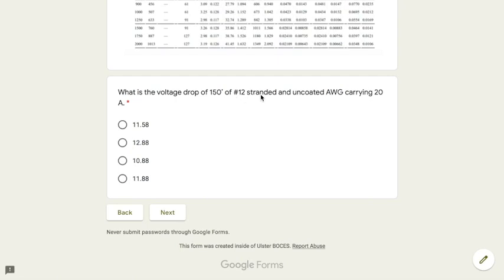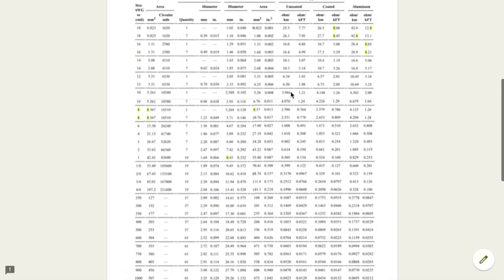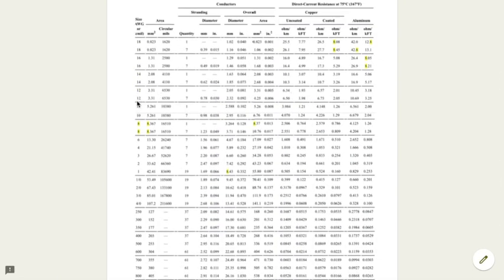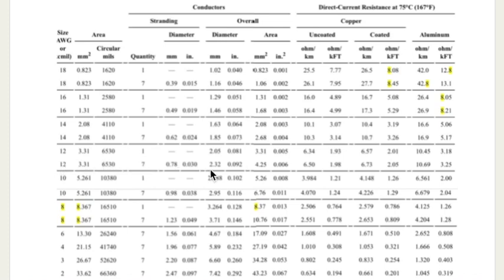12, stranded and uncoated. So I'm going to go up to number 12, and remember stranded will be the second one, and we're going to go uncoated, which will be this side. So it looks to me like I'm looking at a 1.98 right here. So I'm going to plug that in, 1.98.